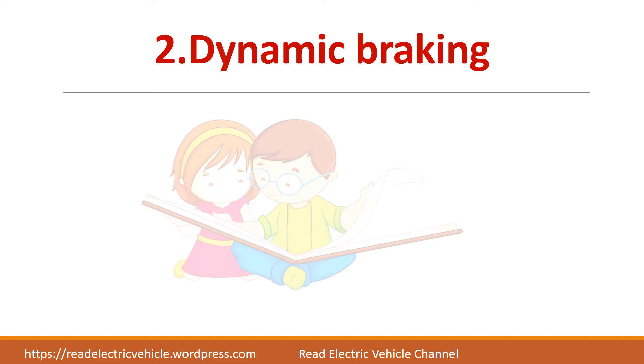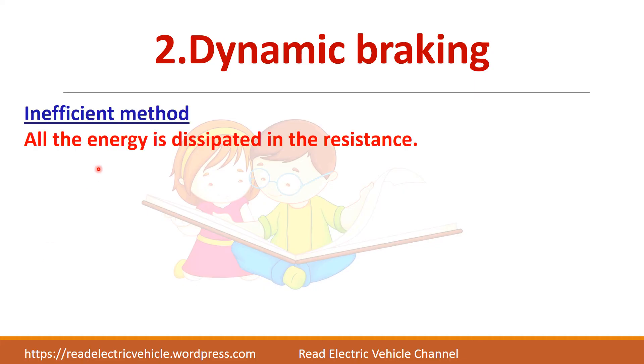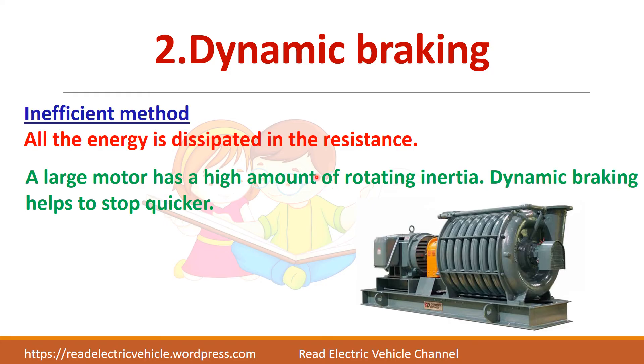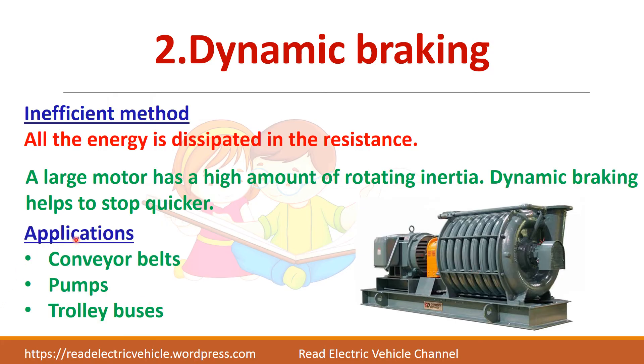Dynamic braking is an inefficient method because all the energy is wasted in the resistance. But we still use dynamic braking because in large motors with high inertia, braking may take a long time, so it may be necessary to stop the motor immediately. A combination of braking methods also helps to stop the motor quickly. This is used in some applications like conveyor belts, pumps, and trolley buses.